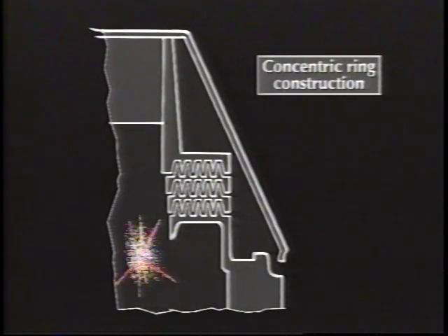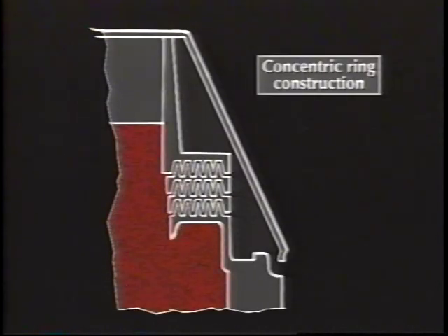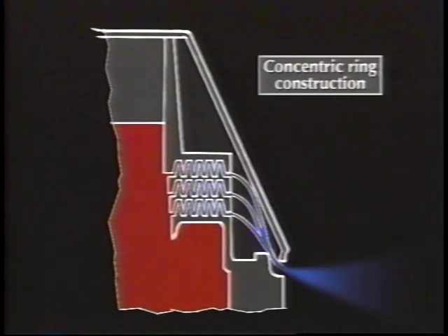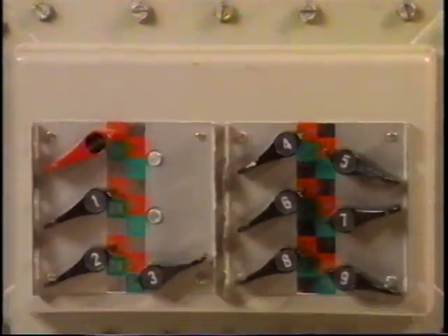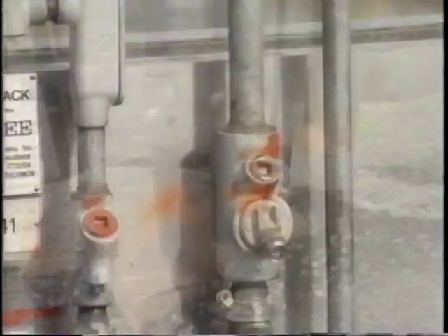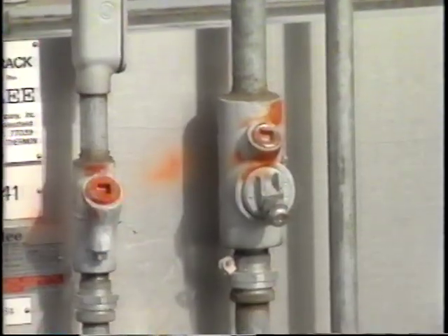Explosion control design works by keeping the explosion inside the enclosure and then very slowly venting and cooling the burning gases. Venting cooled gases prevents ignition of atmospheres outside of the equipment. You also want to confine any explosion to the immediate enclosure area with seal-off fittings.